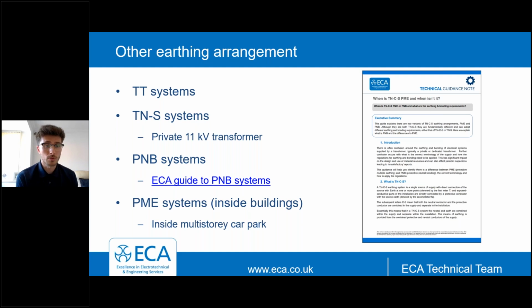There are other systems as well. There's PNB systems, known as protective neutral bonding, and ECA have a guide to PNB systems available to members. Additionally, we've also got PME systems that may be inside buildings, and a common one of that could be inside a multi-storey car park. Again, the regulation around PME I referred to earlier was around outdoor charging points. So you may be able to simplify your design considerably when you have this system present inside of the building.